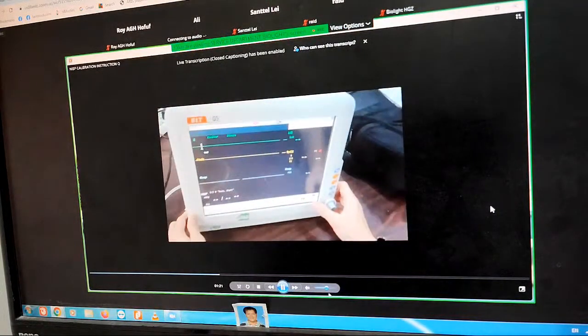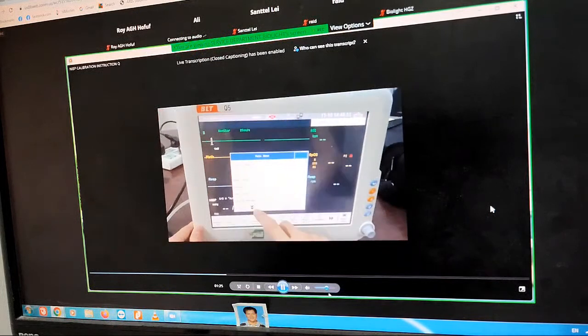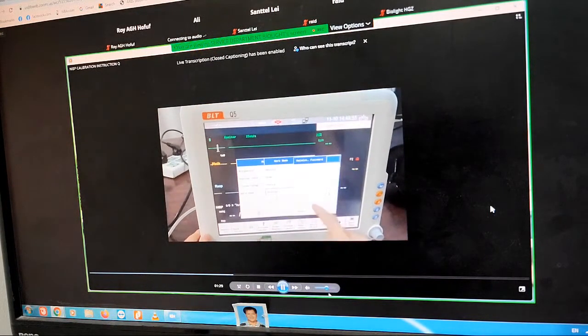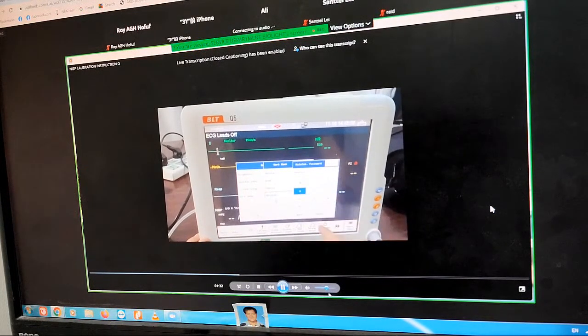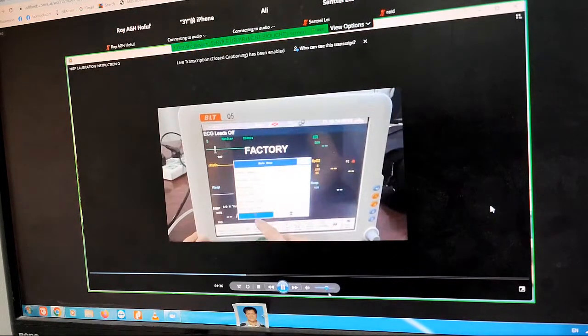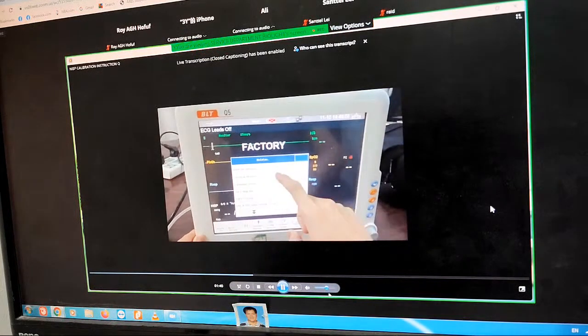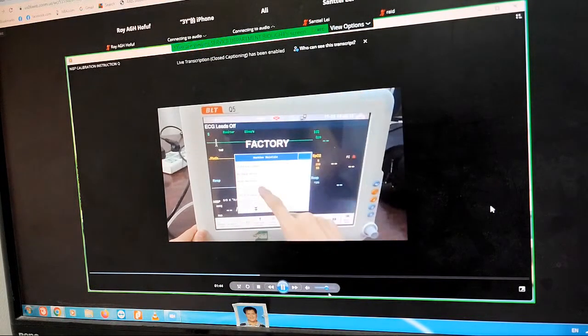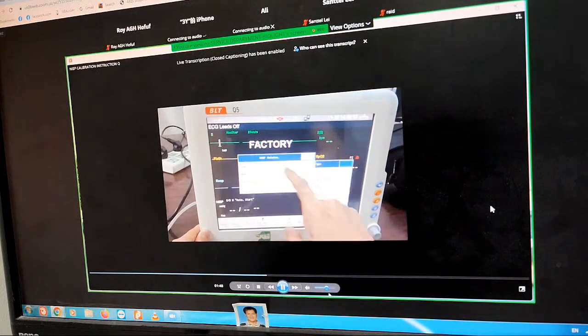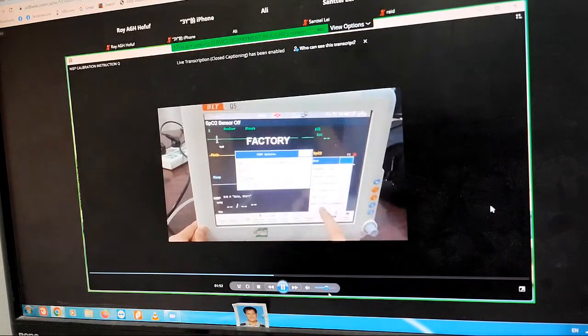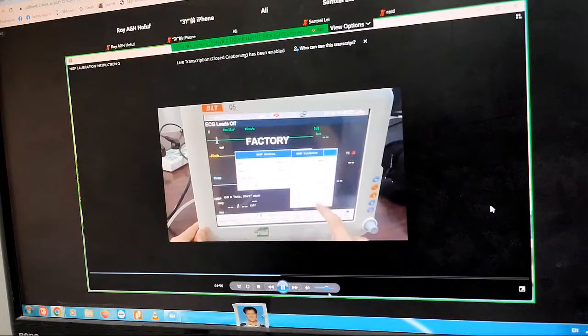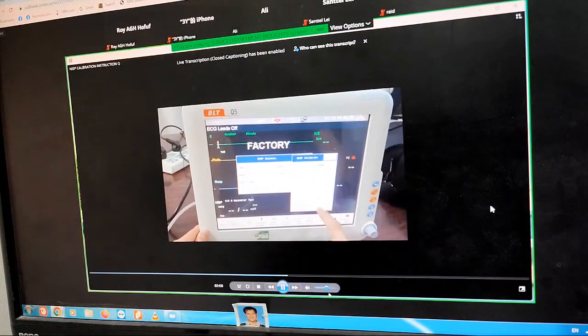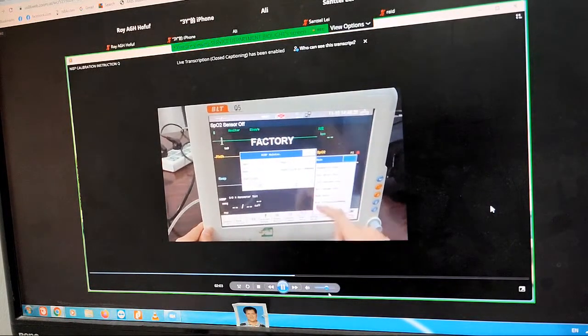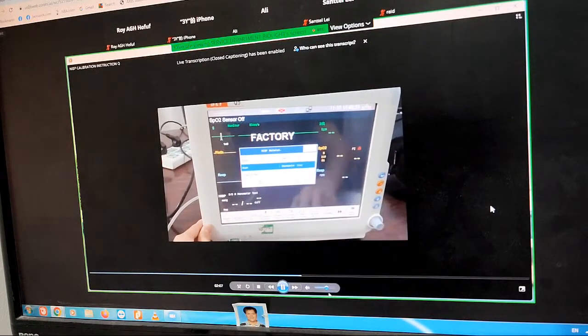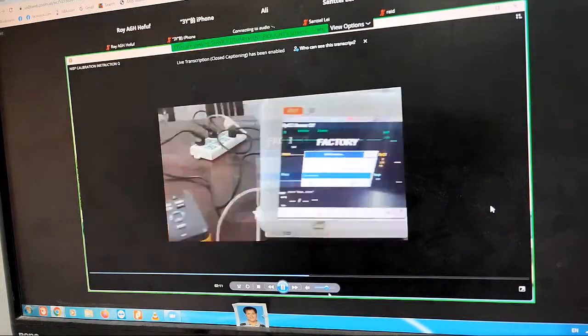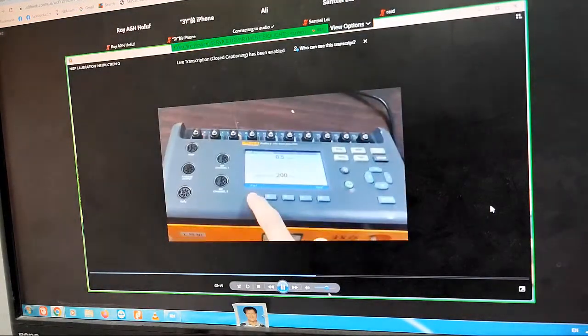Now we're going to maintain the NIBP. For the type, we should choose adult, and for the mode, we should first set the calibration data to 200 millimeters of mercury. Then we should select manometer test, and then press stop. Back on the simulator, we stop it too.